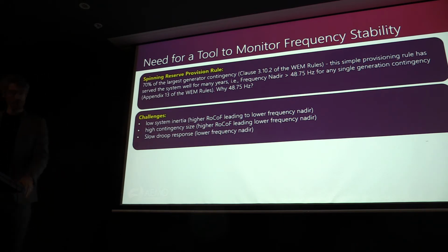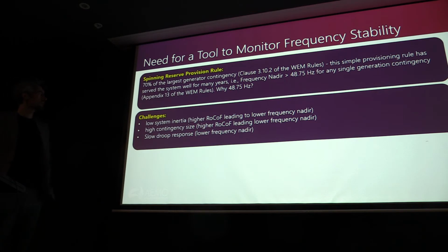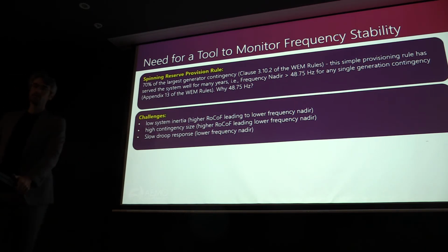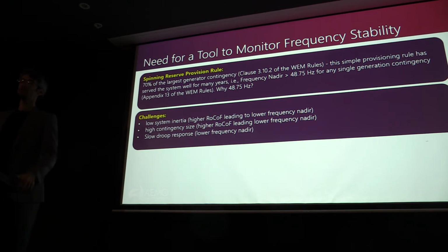Some of the challenges are listed here. Low system inertia: if system inertia declines, we will have higher rate of change of frequency, leading to a lower frequency nadir, making it harder to control the frequency. And we will have high contingency size. For example, with a huge amount of DPV, if we lose a portion of that DPV on top of a utility size generator, the contingency size will be very high as well. That leads to higher rate of change of frequency and a lower frequency nadir, meaning it is harder to arrest the frequency fall after a disturbance.